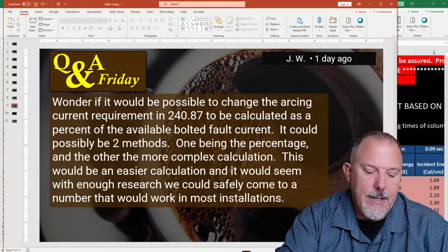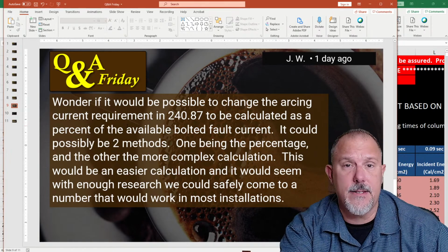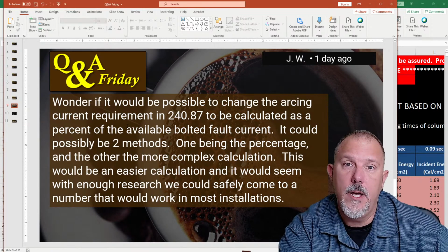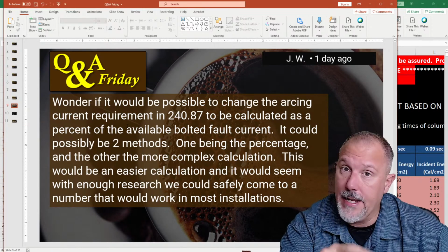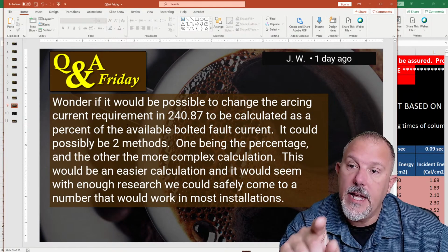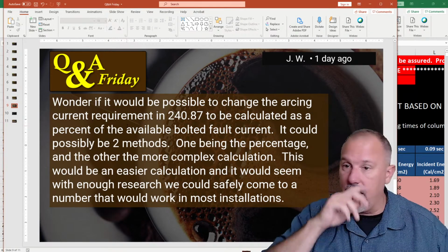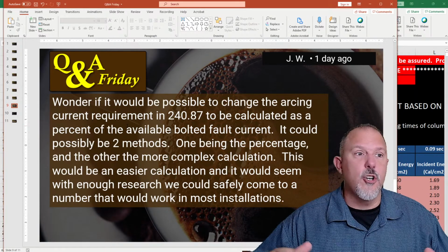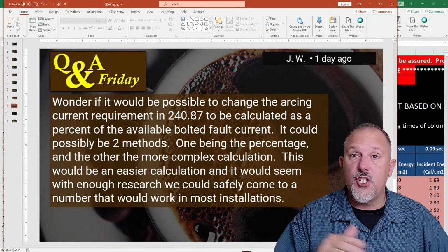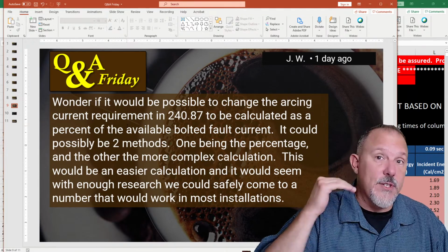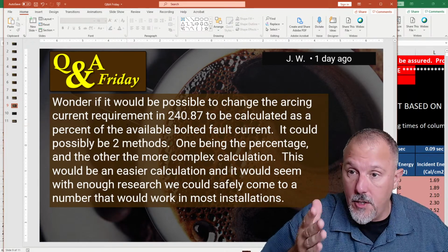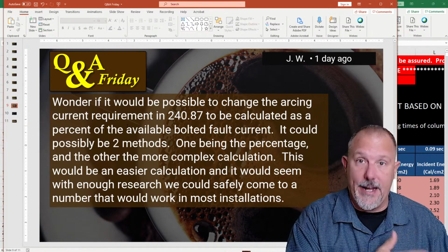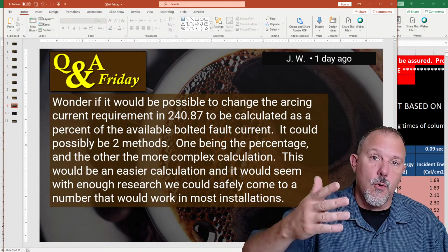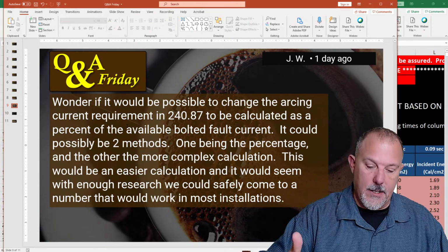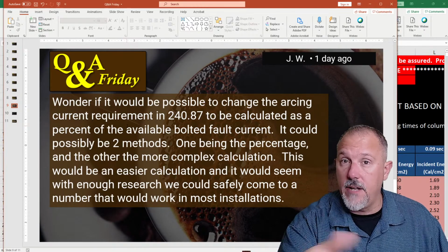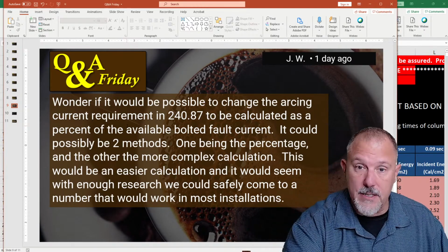you, and I don't care if it's gas insulated, to tell you the truth. What I care about is the voltage I'm looking at in the exposed conductors. If you, Alejandro, take that gas insulated gear and the electrical worker cannot open any piece of this equipment and be exposed to anything that could present an arc flash hazard, then there would be no reason for a label, because there is no arc flash hazard. If all of the doors open up to low voltage wiring, and we can have the debate on whether or not you can have an arc flash on 120 volts, I would say no, you can't.